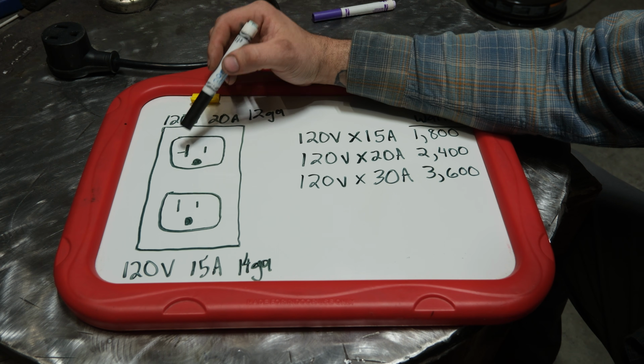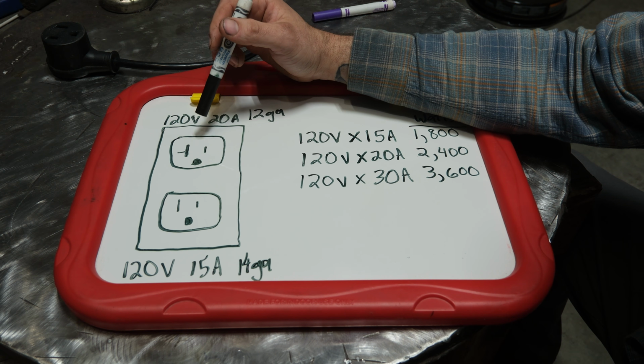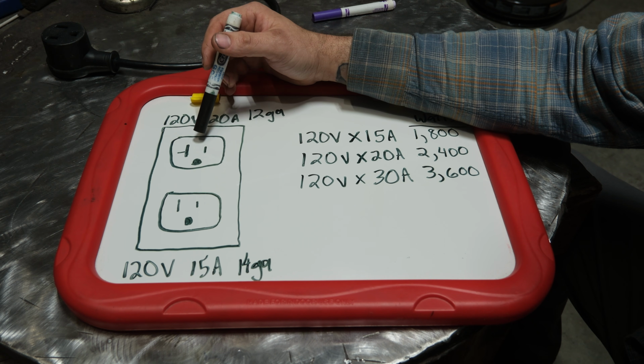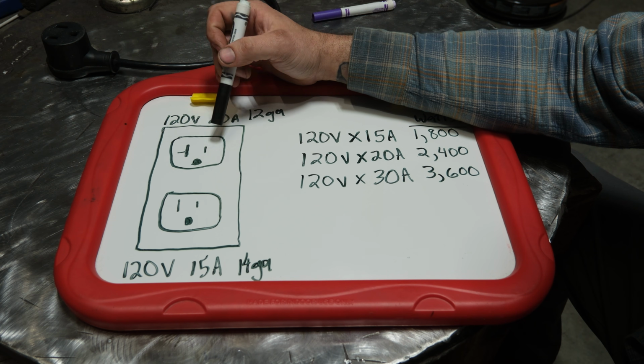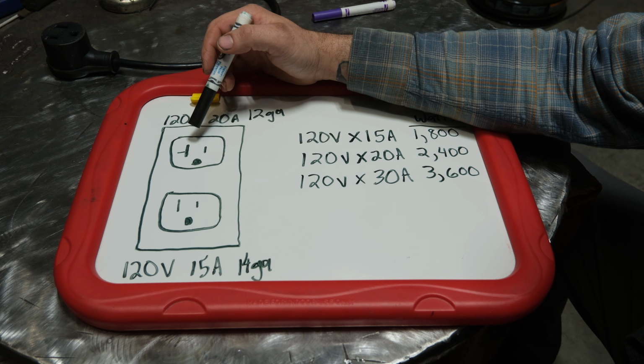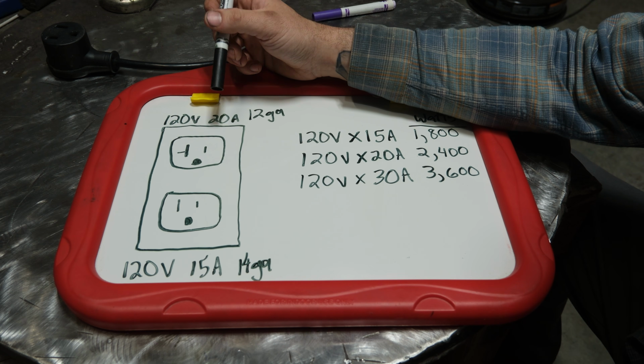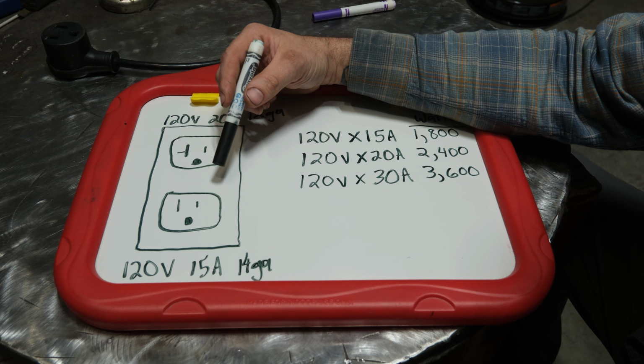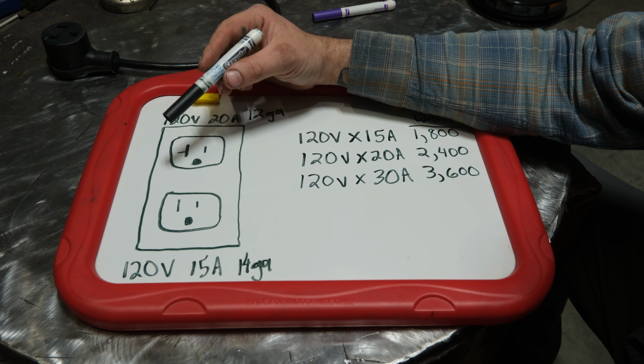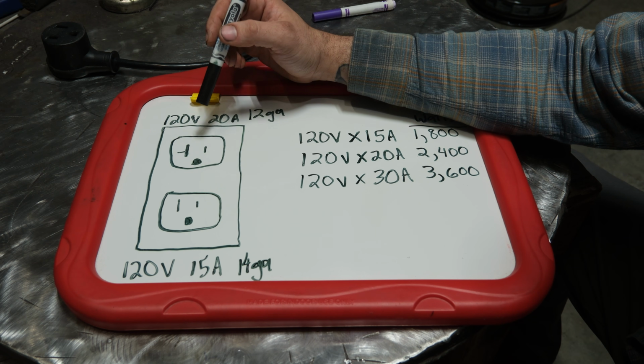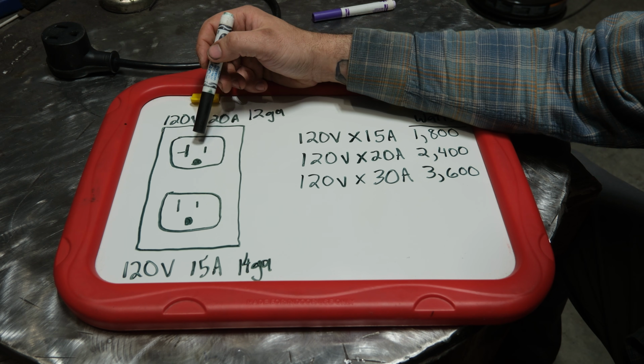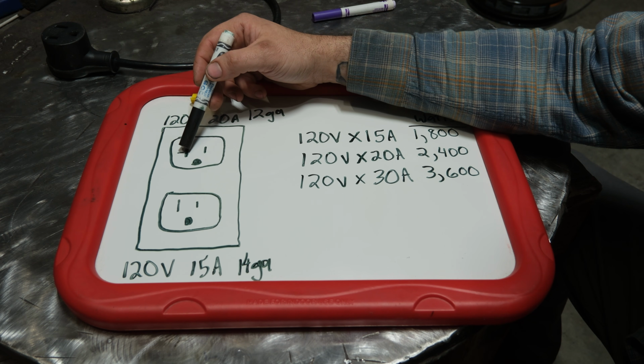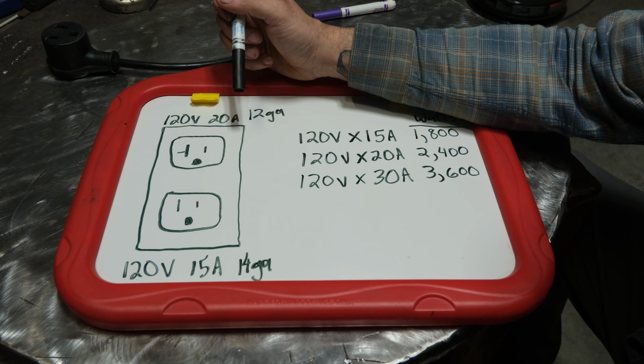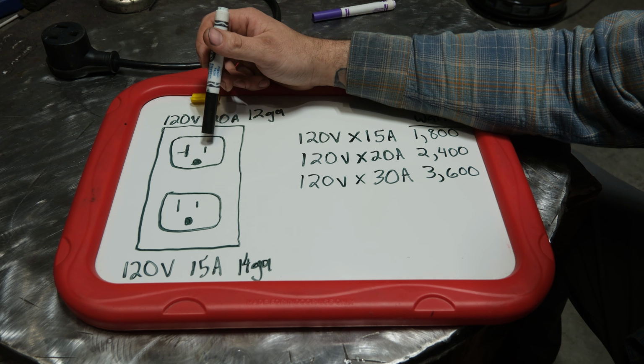Now, this is technically what should be hooked to a 20 amp breaker. However, due to the electrical code here in this country, you can actually find 20 amp breakers hooked to what is a 15 amp plug. And I'm not going to get into the whole deal behind that because that's a whole other topic. But what you need to know is that if you see an outlet like this with a sideways slot in it, then you have a 20 amp circuit.